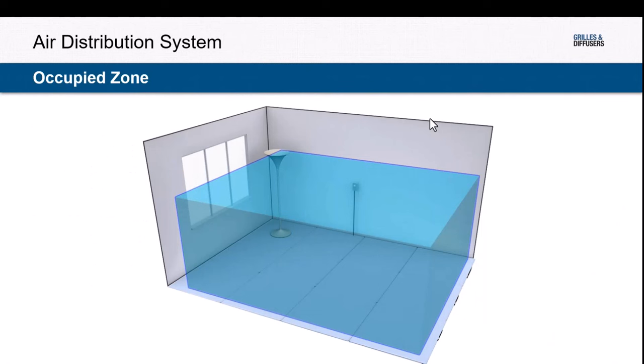So what is the occupied zone? We define it as six feet above the finished floor, one foot off an interior wall, and three feet off an exterior wall. That's ASHRAE defining that six-foot level. In exterior or perimeter spaces, a lot of times we are trying to wash the window — basically treating the glazing on the exterior of the building from floor to ceiling — to minimize drafts in that space.